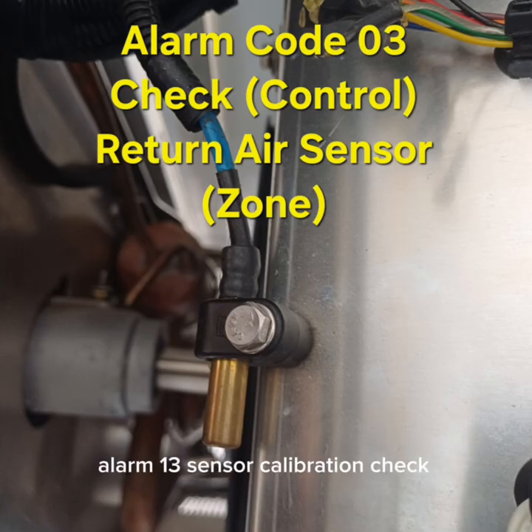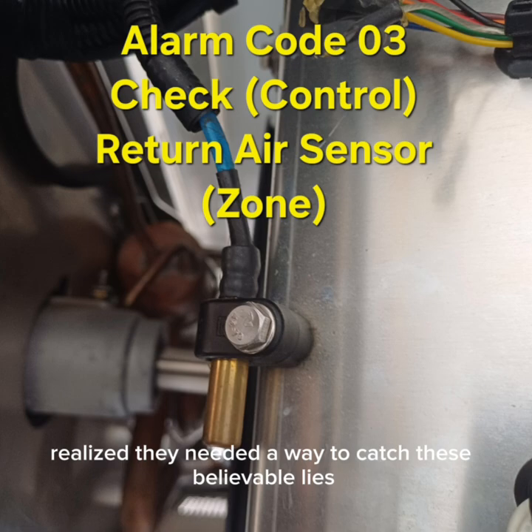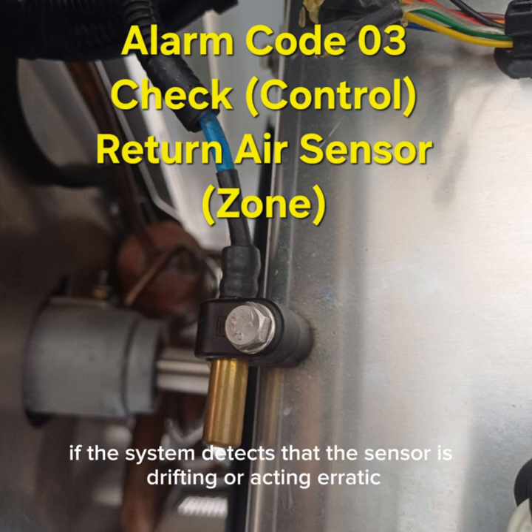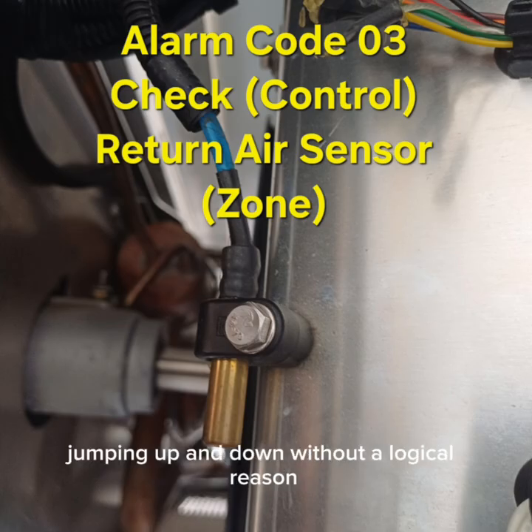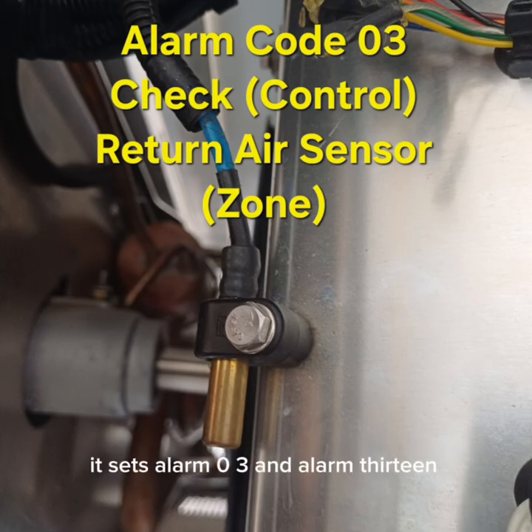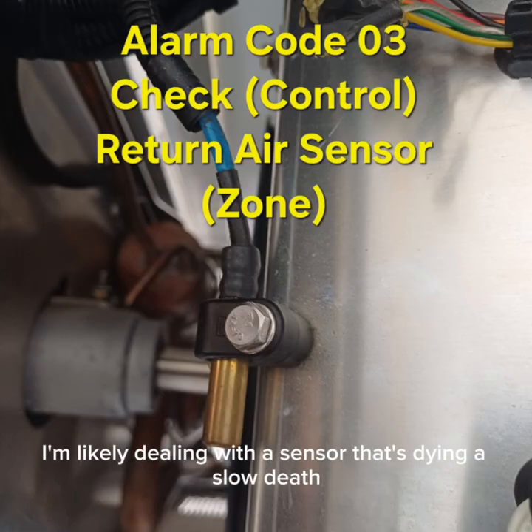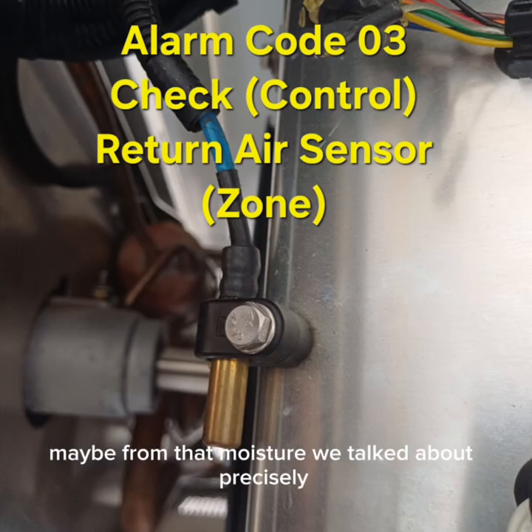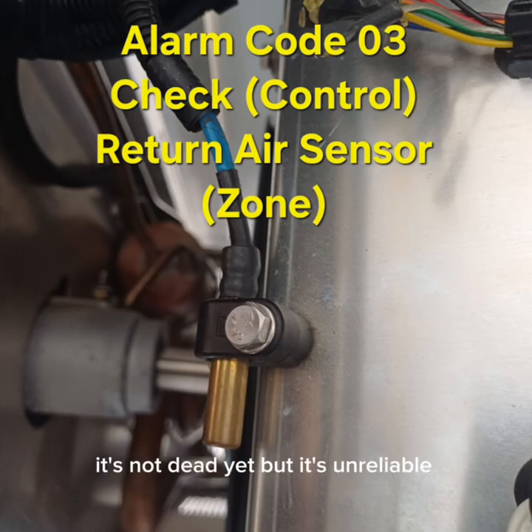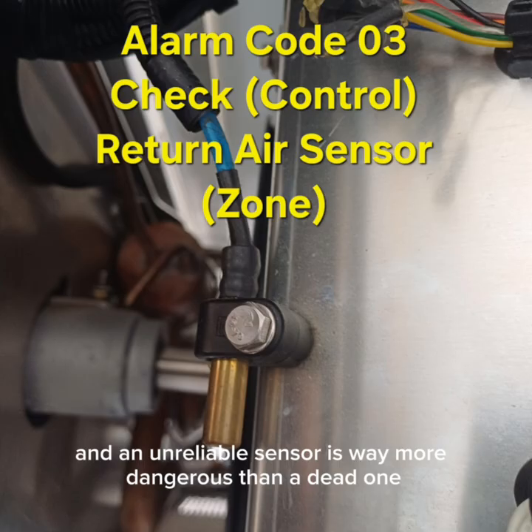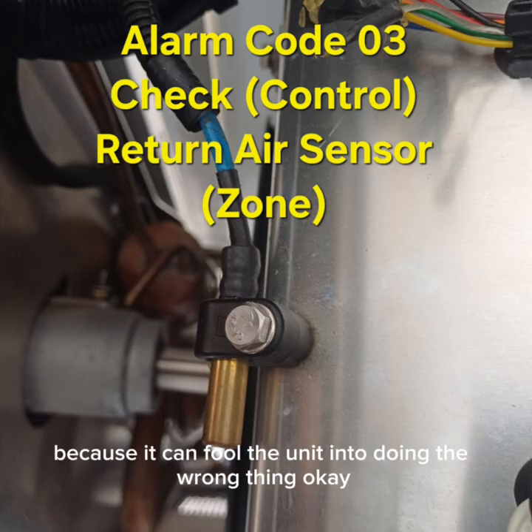Alarm 13, sensor calibration check. The engineers realized they needed a way to catch these believable lies. If the system detects that the sensor is drifting or acting erratic, jumping up and down without a logical reason, it sets alarm 03 and alarm 13. So if I see code 03 and code 13 together, I'm likely dealing with a sensor that's dying a slow death, maybe from that moisture we talked about. Precisely. It's not dead yet, but it's unreliable. And an unreliable sensor is way more dangerous than a dead one because it can fool the unit into doing the wrong thing. Okay, that makes sense.